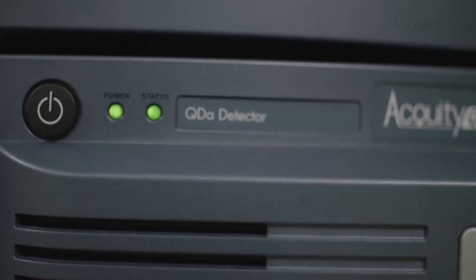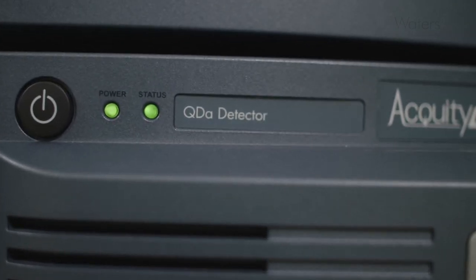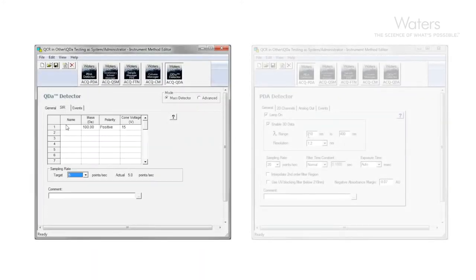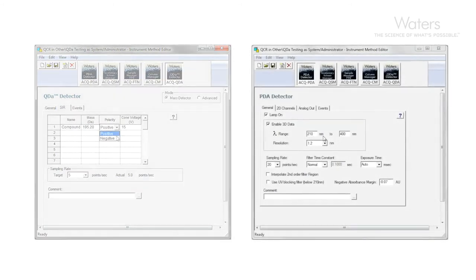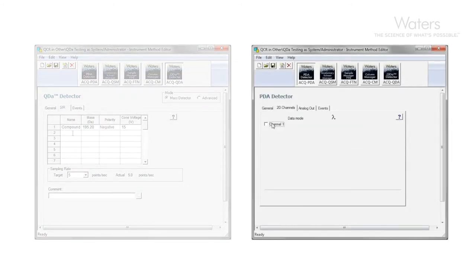As with a photodiode array detector, the Acquity QDa has two modes of operation. We can acquire full spectral data or we can look for single ions. We do this by selecting a specific mass in the Acquity QDa method. And this is something that you are familiar with when using a specific wavelength on a photodiode array.